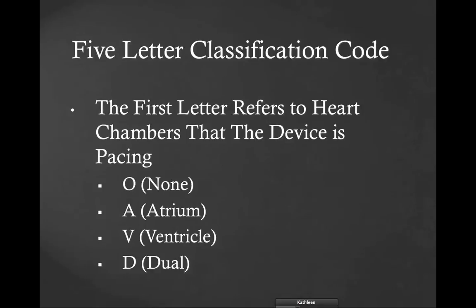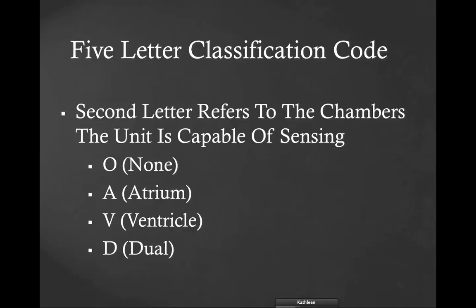The 5-letter classification code, the first letter refers to the heart chamber that the device is pacing in. It can be either O, none, A, atria, V, ventricle, or D, dual. So the first letter stands for where the actual wire is in the heart, where the chamber that the device is pacing in. The second letter indicates which chamber electrical impulses the unit is capable of sensing, such as the above pacing codes. Where is it sensing? Most likely, if it's dual, it's going to sense in both atria and ventricle.